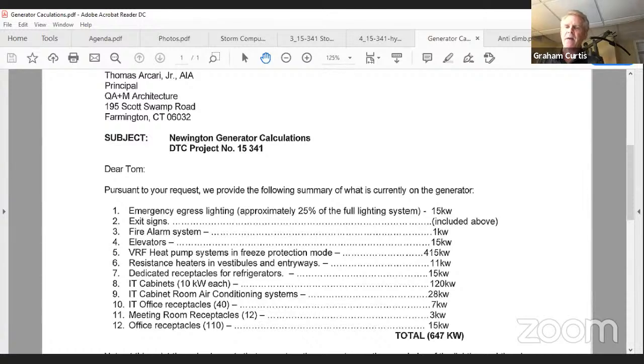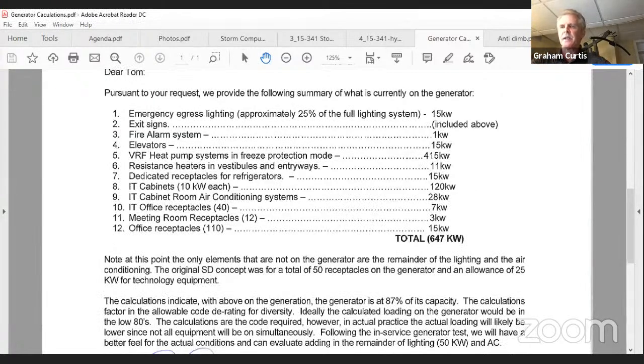So if you look at the math, the total adds up to 647, which is actually greater than the 600 size. So you would question, how can that be? Well, the National Electric Code allows you to reduce the generator size based on the assumption that not all these things are going to work simultaneously. So there's a diversity of load, which allows you to reduce that load significantly or proportionally. So currently, if you do that calculation by code, you're under 600, but you're in that range.